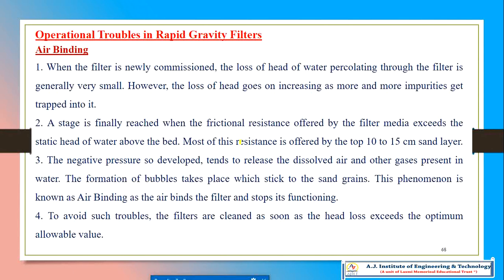Because of the resistance offered, that will be there in the top 15 cm layer of the sand. What happens? At that time negative pressure will be there. This negative pressure so developed tends to release the dissolved air and other gases present in the water. So the formation of bubbles takes place, which stick on the sand grains. This phenomenon is air binding, and the air-bound filter stops functioning.